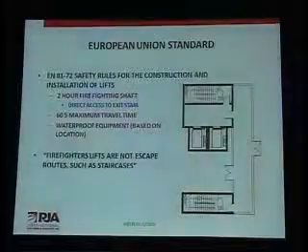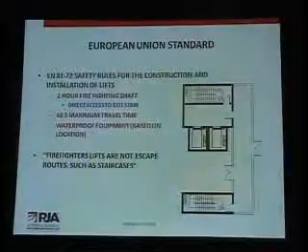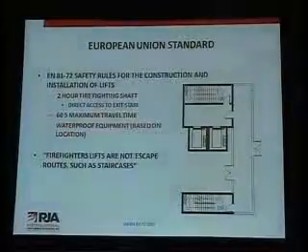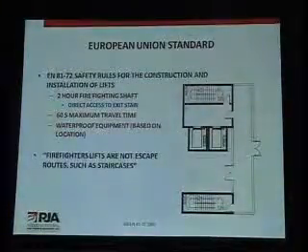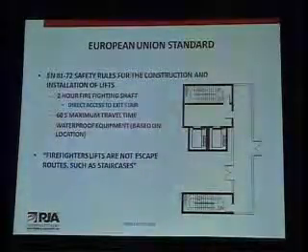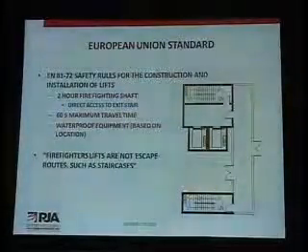Moving on into the European Union standard, Jim had touched on it briefly regarding a firefighter shaft. Essentially this is a 2-hour rated enclosure that not only provides a vestibule and a landing area for firefighters to stage operations, but it also provides a secondary means of access and escape via the stair that's directly connected to the vestibule.